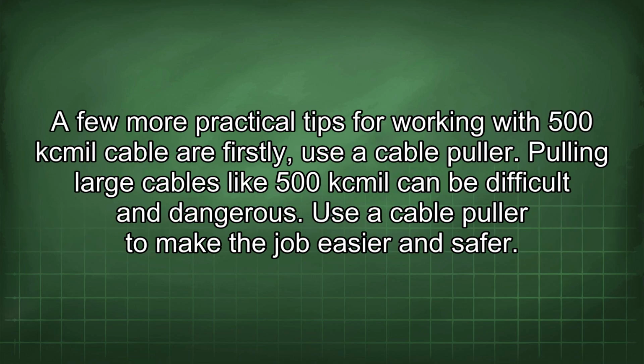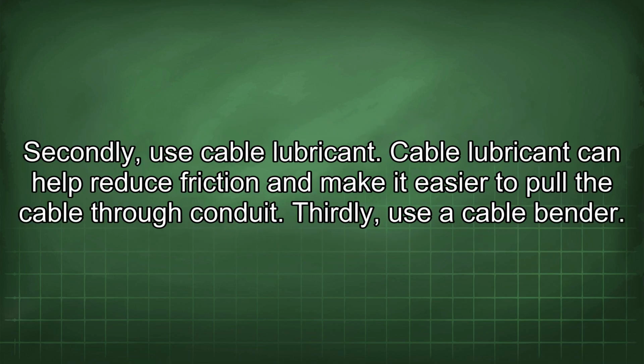A few more practical tips for working with 500 kcmil cable are: firstly, use a cable puller. Pulling large cables like 500 kcmil can be difficult and dangerous. Use a cable puller to make the job easier and safer. Secondly, use cable lubricant. Cable lubricant can help reduce friction and make it easier to pull the cable through conduit.